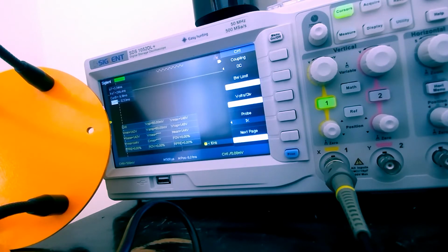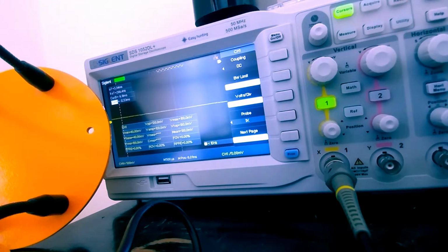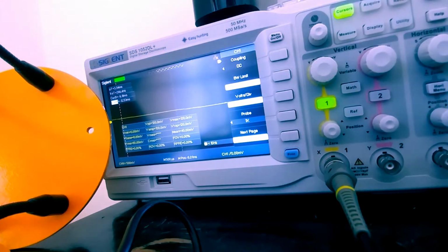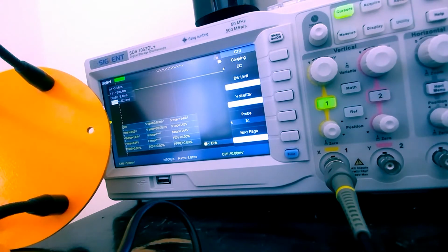But the thing I'm looking for on that yellow line specifically, when I connect my leads to it, is I don't want to see a lot of spurious movement, what we call peaks and jagged edges. Why is that important? Well, if I'm taking a voltage measurement and that DC voltage is very dirty, or it starts to oscillate, meaning you see a change instead of it being constant, looking more like a traditional sine wave, then there's something wrong with the conversion from AC to DC. Maybe there's a bad filter, or the semiconductor devices, the diodes, the bridge rectifier, whatever it is, and that's one surefire way to check.